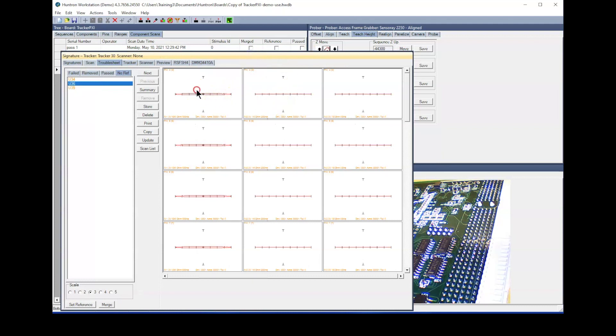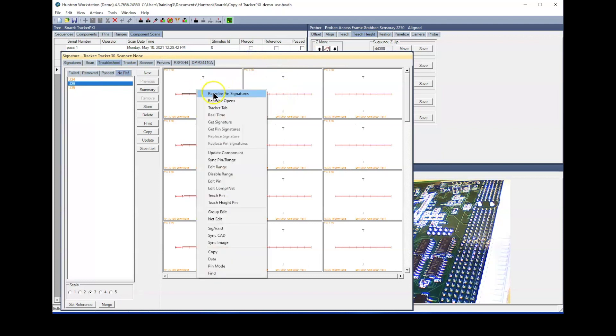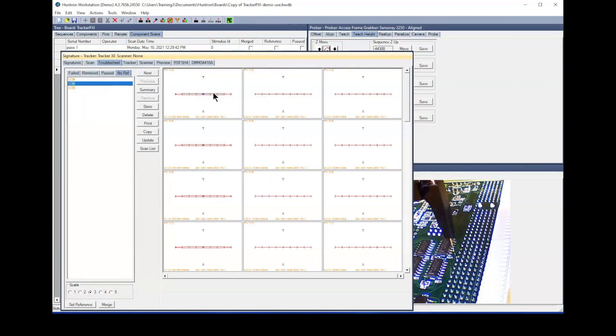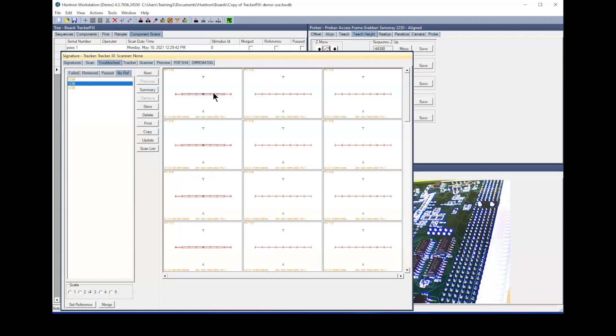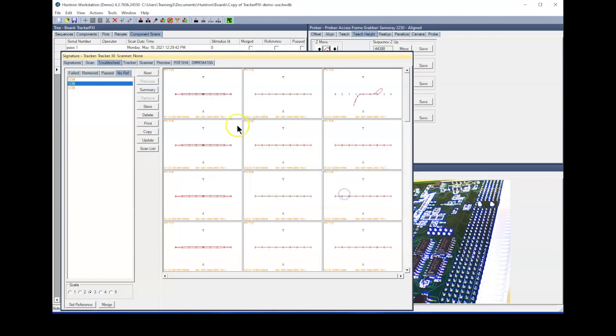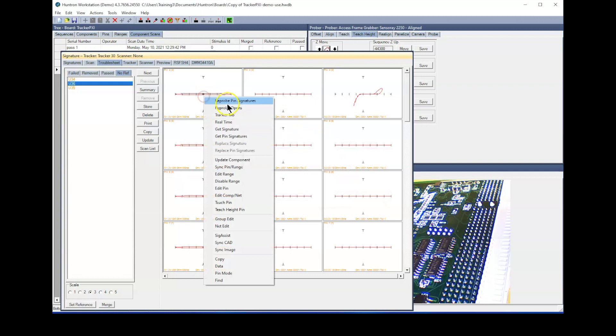If you are testing in multiple ranges, set your scale so you can see all of the signatures for a pin. Right click in a signature box to display the menu. Select Reprobe Pin Signatures at the top of the menu.